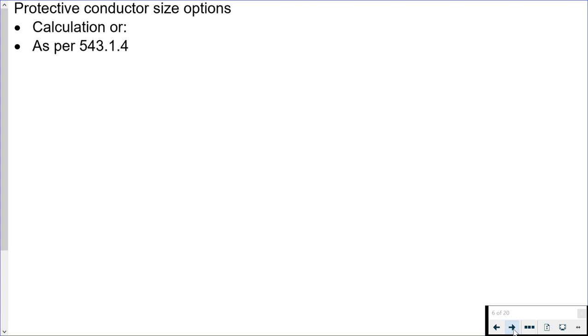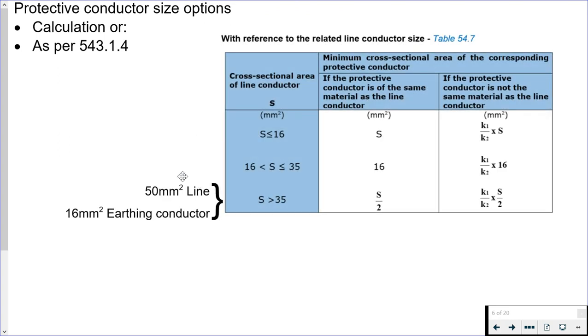When it comes to checking for our protective conductor size options, we have two options: we can check it by calculation or as per regulation 543.1.4. 543.1.4 basically tells us to look in table 54.7.